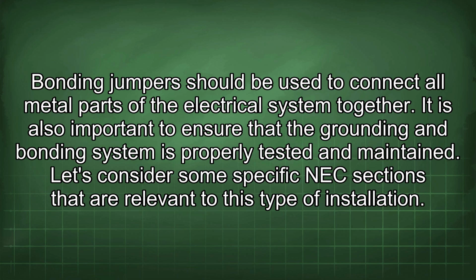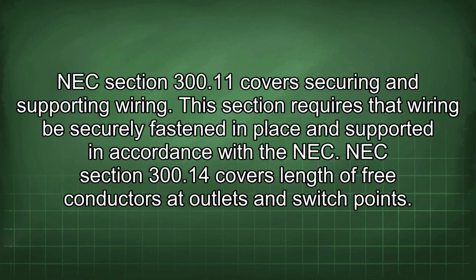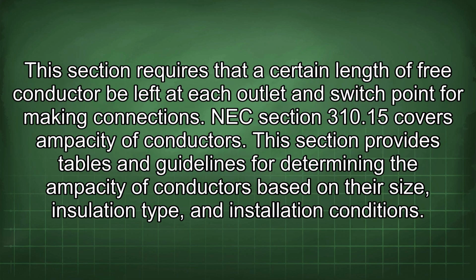Let's consider some specific NEC sections that are relevant to this type of installation. NEC Section 300.11 covers securing and supporting wiring. This section requires that wiring be securely fastened in place and supported in accordance with the NEC. NEC Section 300.14 covers length of free conductors at outlets and switch points. This section requires that a certain length of free conductor be left at each outlet and switch point for making connections. NEC Section 310.15 covers ampacity of conductors.